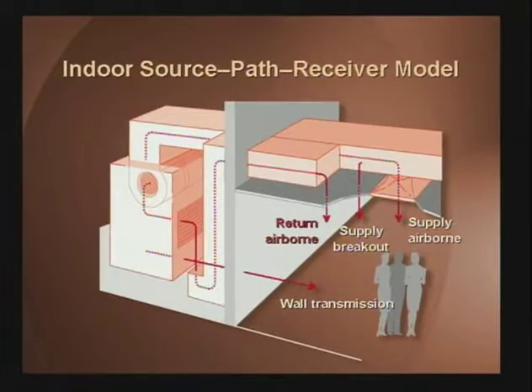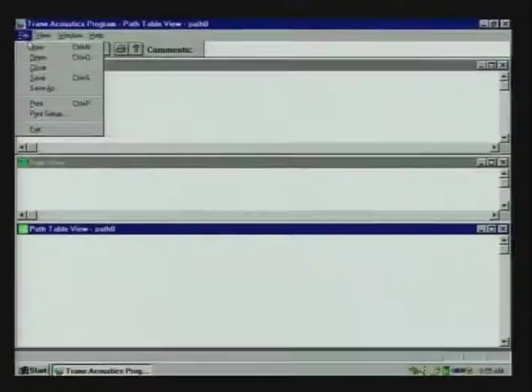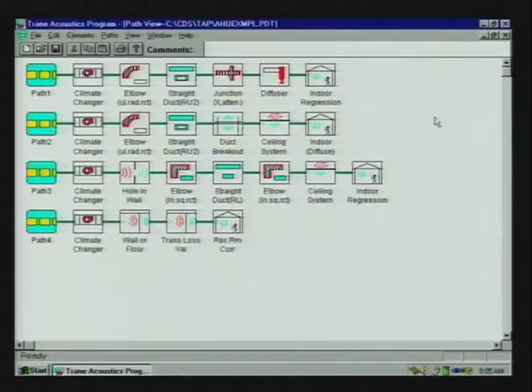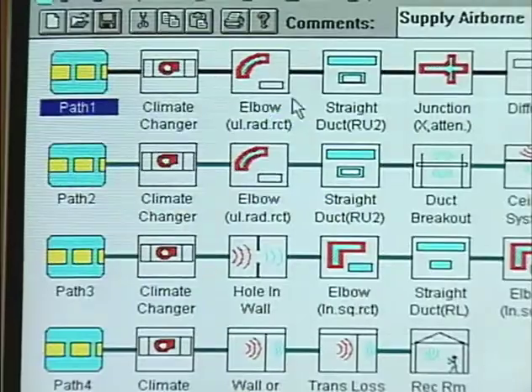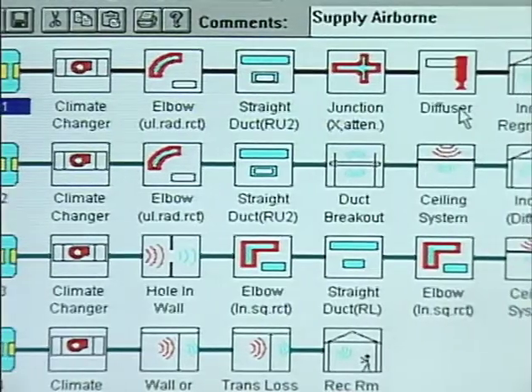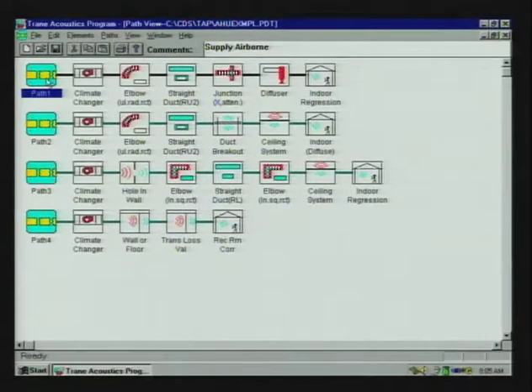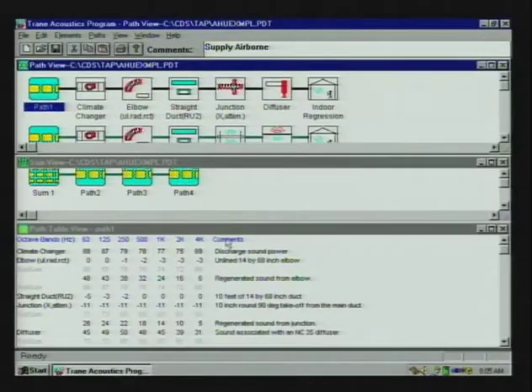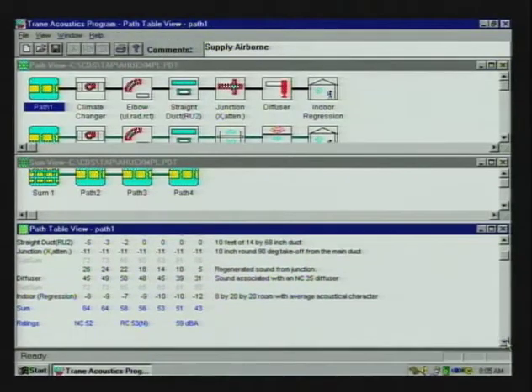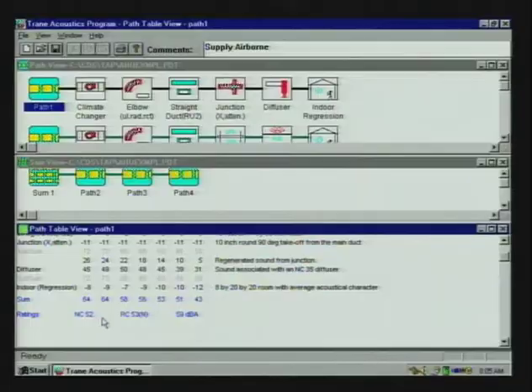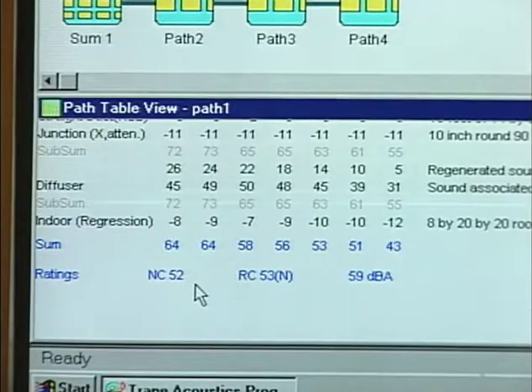We've already identified that there are 4 paths involved here. To save some time, I've modeled this already, and I'm just going to open that file up. You can see here, let me just expand this window. Here are the 4 paths that we've modeled. Each path starts with the equipment sound data, and then elements are added one at a time that describe the portions of that path. I have the supply airborne selected here. We go down and show you in the table view. Down at the bottom, table view shows you the tabular data for each of those elements, and it also calculates an NC value. In this case, path 1, our supply airborne path, is coming in at an NC 52.